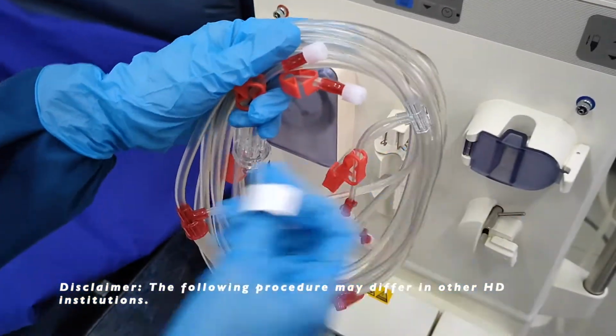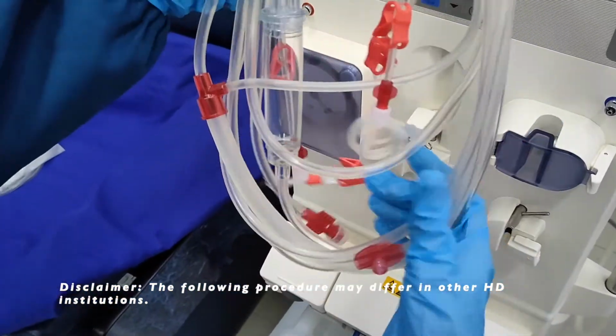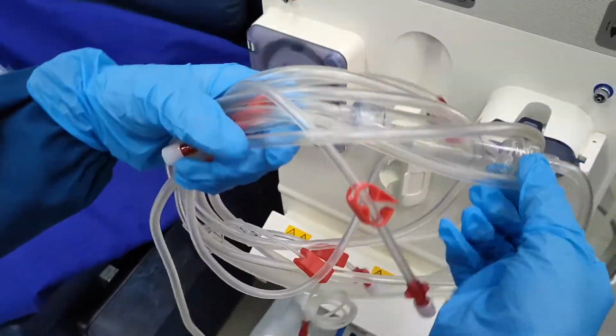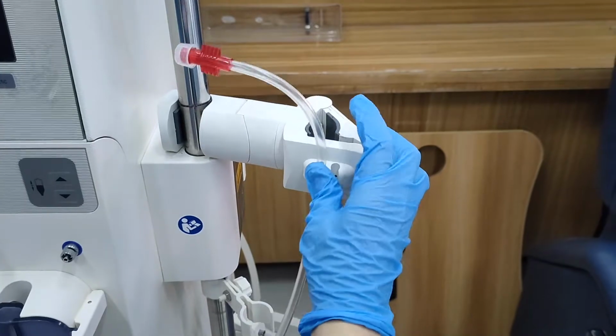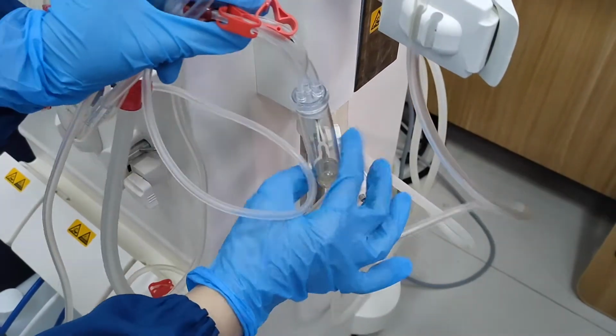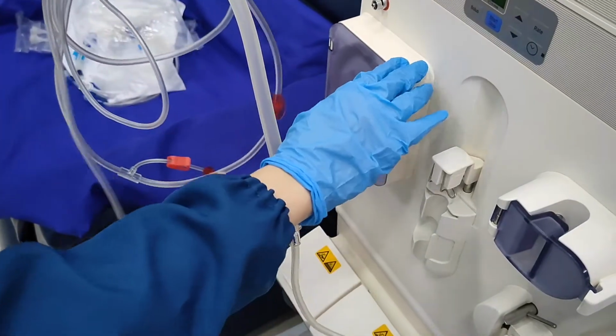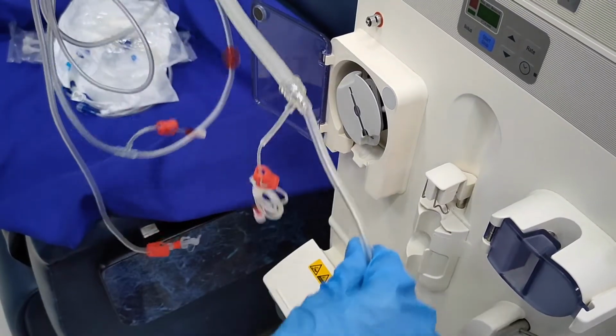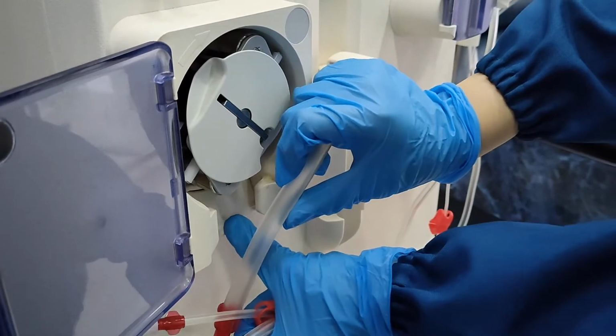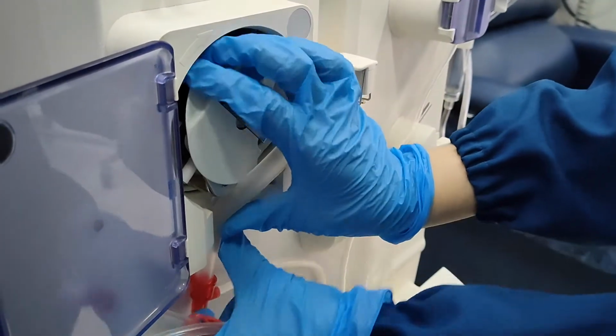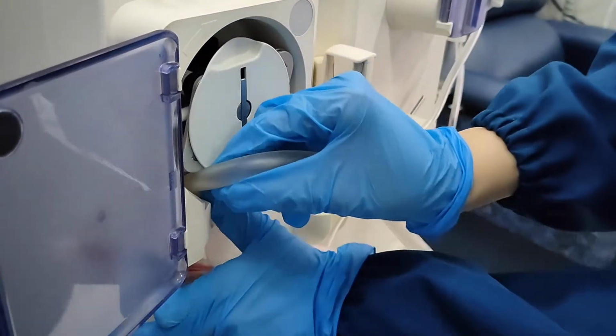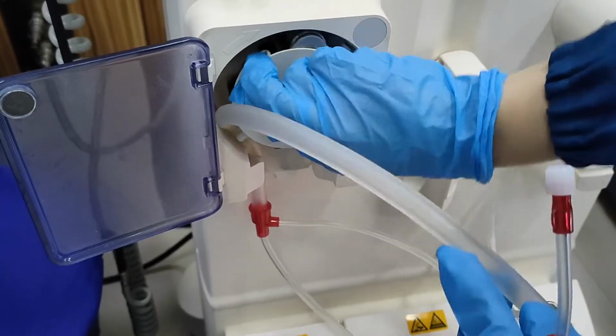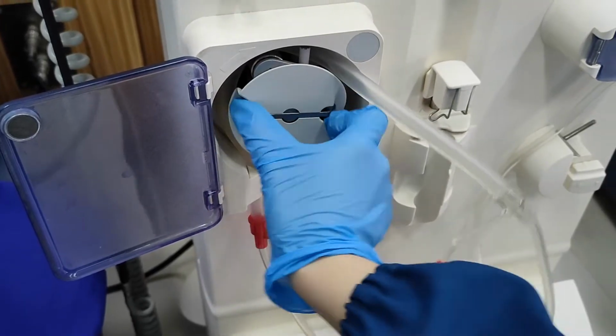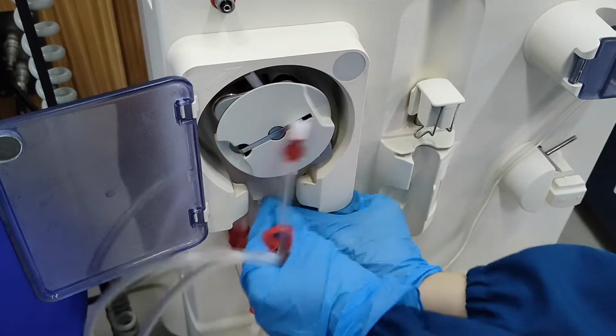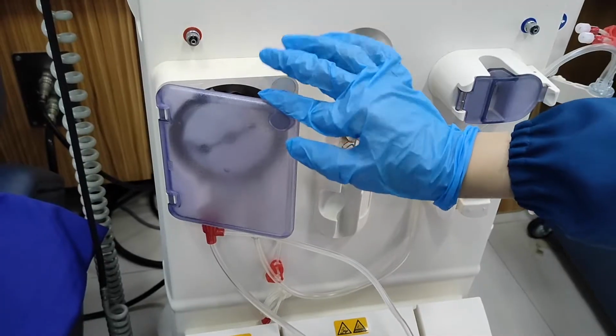Bloodlines. The following procedure may differ in other HD institutions. First, take the arterial bloodline. Hang the arterial dialyzer port to a dialyzer holder. Then put the arterial chamber in place. Open the blood pump and place or thread the blood pump segment into the blood pump. Then, temporarily set aside the arterial end.